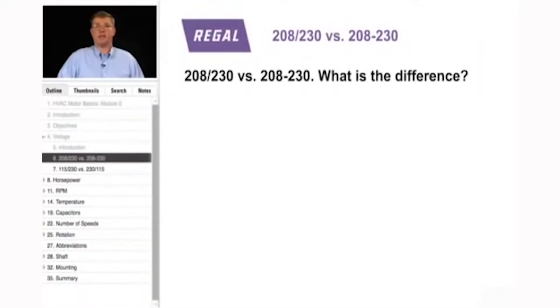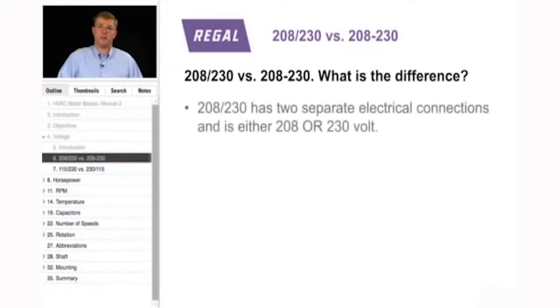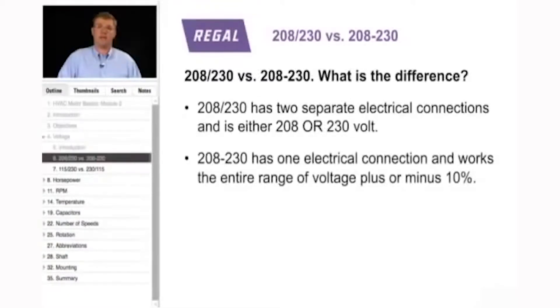A commonly mistaken area involves the difference between a 208/230 dual voltage motor and a 208-230 motor. A 208/230 dual voltage motor has two separate electrical connections and is either 208 volt or must be reconnected for 230. The other type, a 208-230 motor, has one electrical connection and will work across the entire range of 208-230 plus or minus 10% on one electrical connection.